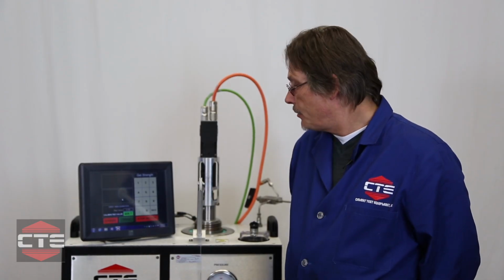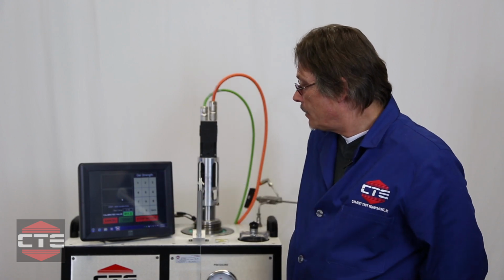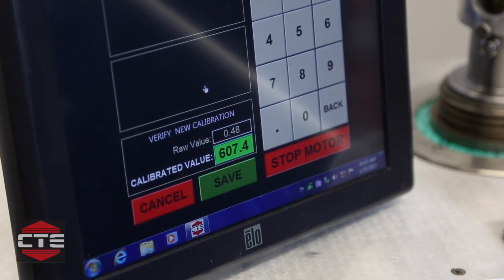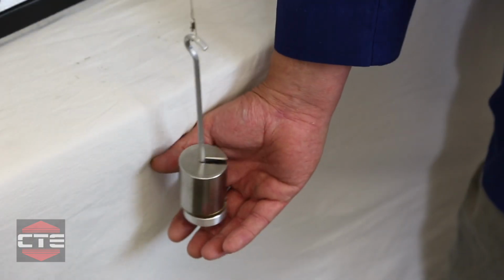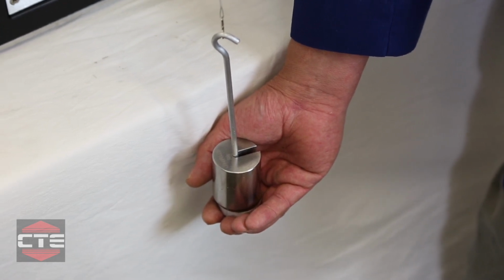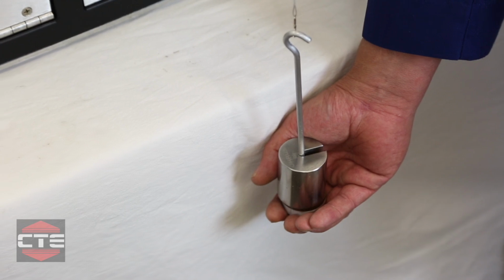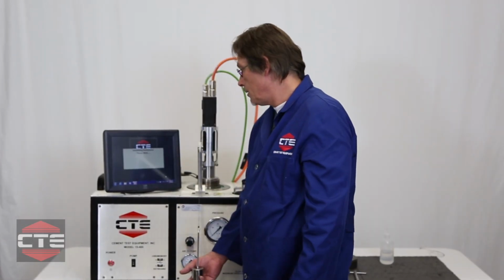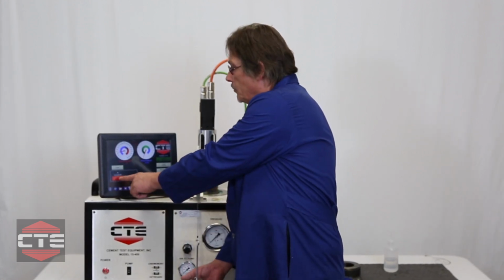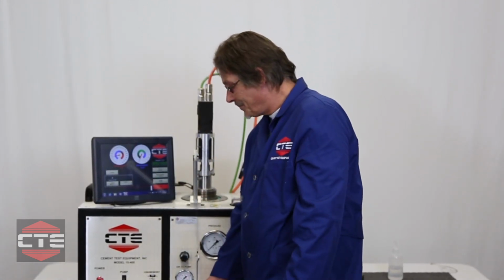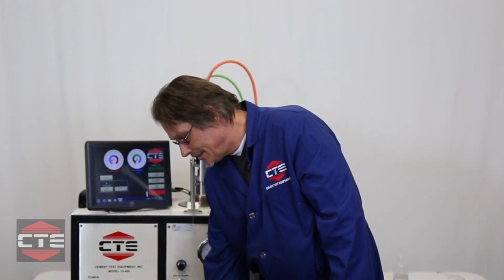After we've entered our low and high values, your calibrated value shown here in the green box, you want to make sure that that number does not stray plus or minus 25 from the 600. You will see it fluctuate above 600 and below 600, but never more than 25. As long as you have a fluctuation above and below the 600, you will never read a steady number on here. You'll know your calibration is good. After you're satisfied you have a good gel calibration, be sure to support your weights. Hit your save button, and again you'll be prompted to save. Switch your motor to stop, supporting the weights, and that completes the gel calibration.